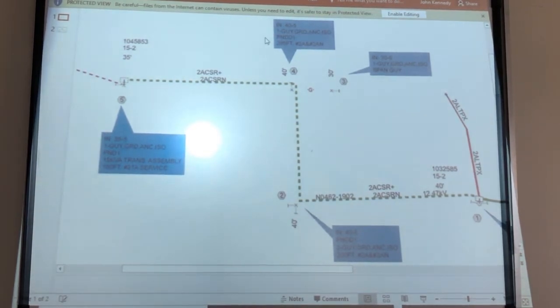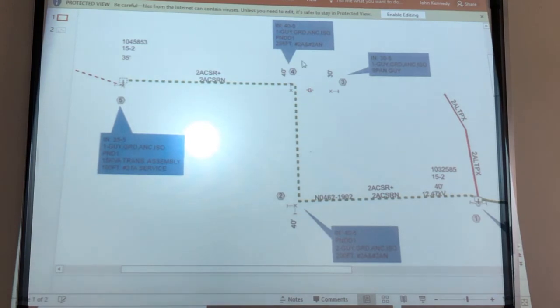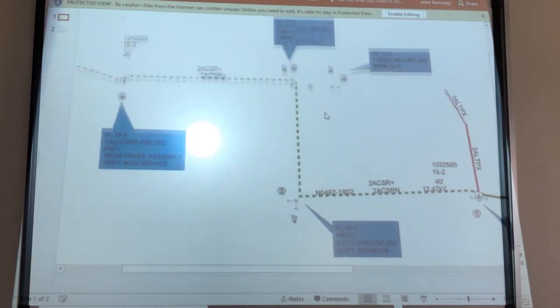That includes a 40-foot class 5 pole, one down guy, double dead end, which is the wires dead end in this direction and dead end in this direction, with the wire span being 295 feet times 2. You've got to remember that. That's times 2 for your primary and your neutral. This span guy is galvanized wire that you would be using on all your down guy installations. So at this point, you're ready to move to location 2.